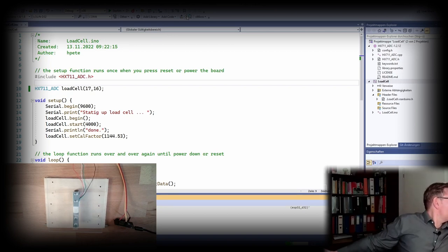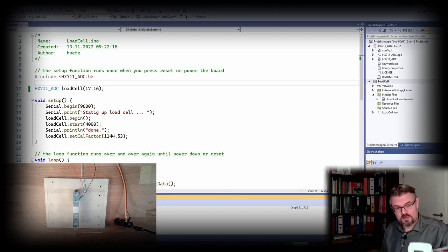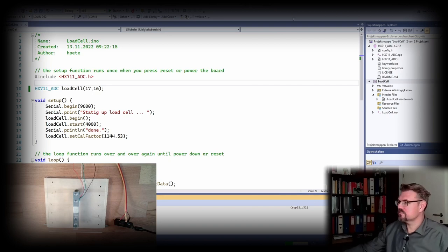I remember that this here was 525 grams. This is what I remember. So I will use this as reference weight. Because I honestly think this calibration factor is somehow reflecting this voltage change. So we would need a different calibration factor. Pretty sure. Then I will try. So okay, uploading. Because I think maybe we don't have to calibrate, just... I'll show you afterwards what I mean.